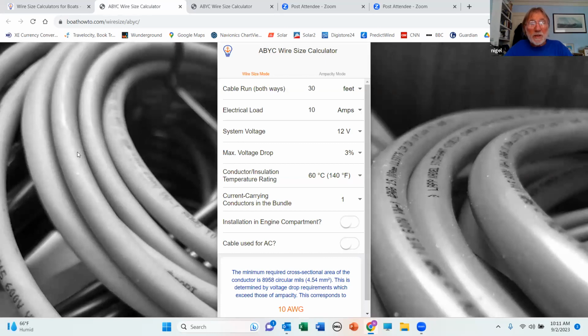When we go into the ABYC one, we've got a choice of wire size mode or ampacity mode. So now we're going to enter the length of the circuit. I put 30 feet in here. It's a fairly long conductor run. Remember, this is in both directions. It's from the positive to the load and then back with the negative. And then we've got to put the load in. To find that out, you'll have to look at the literature that comes with whatever it is you're powering up. And if you've got multiple devices on a circuit, then you need to add up all the loads and find out what the worst case load is.